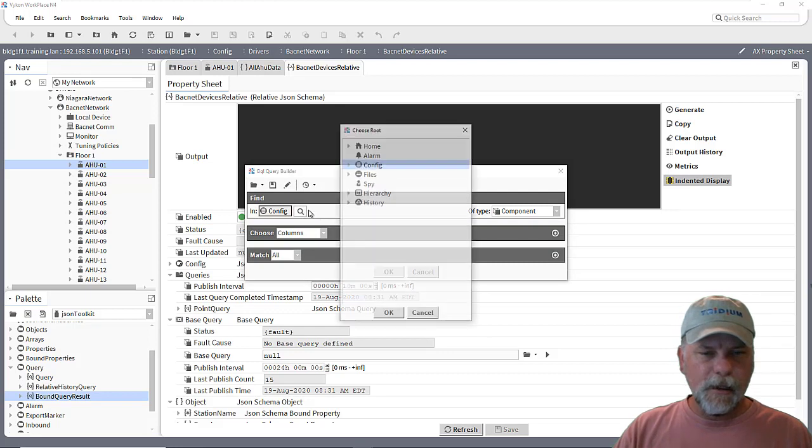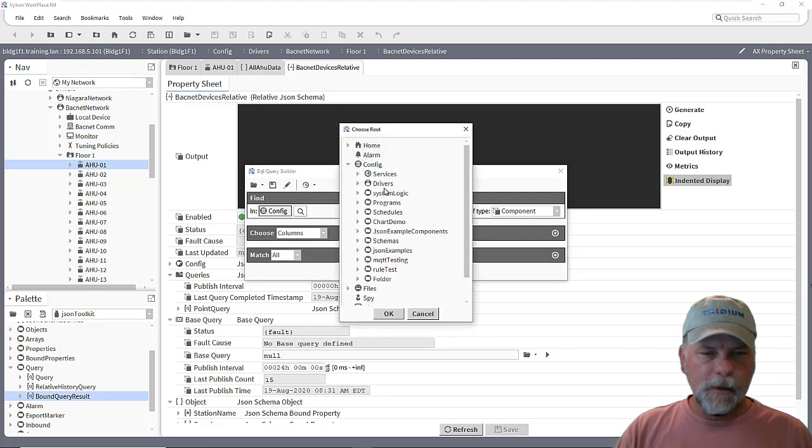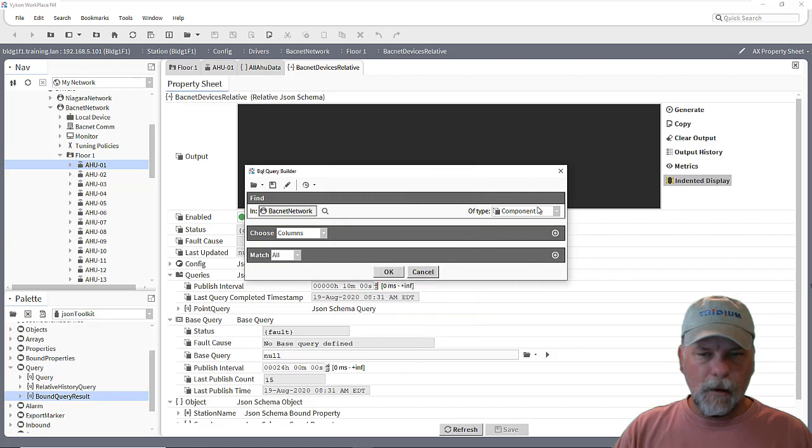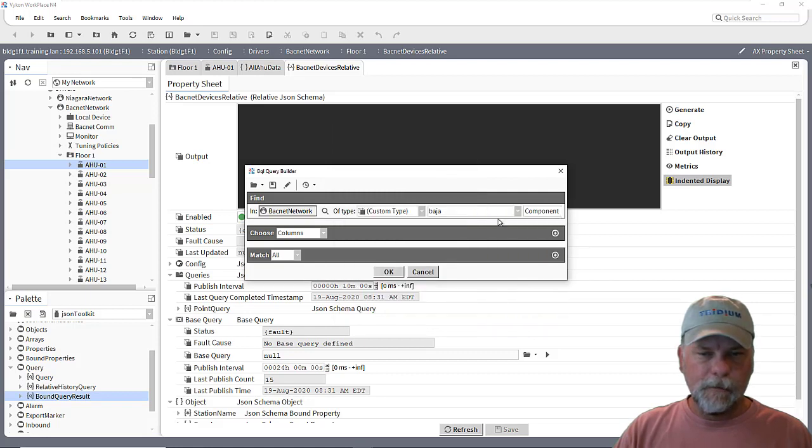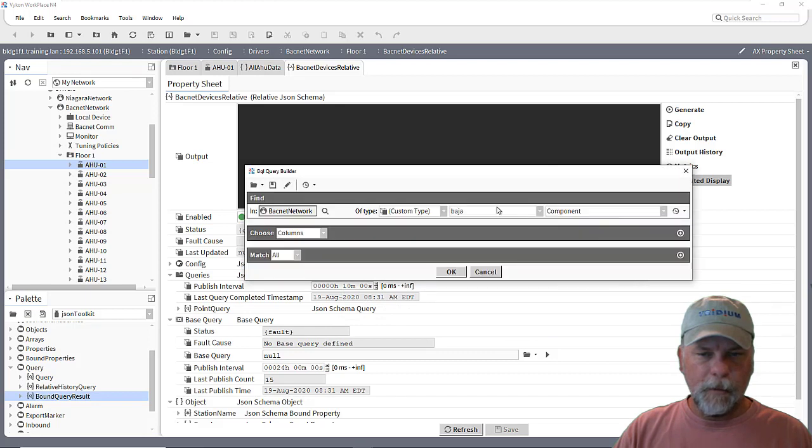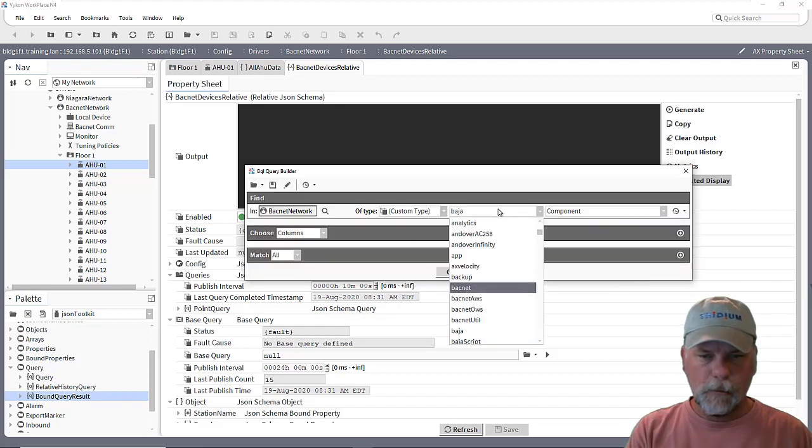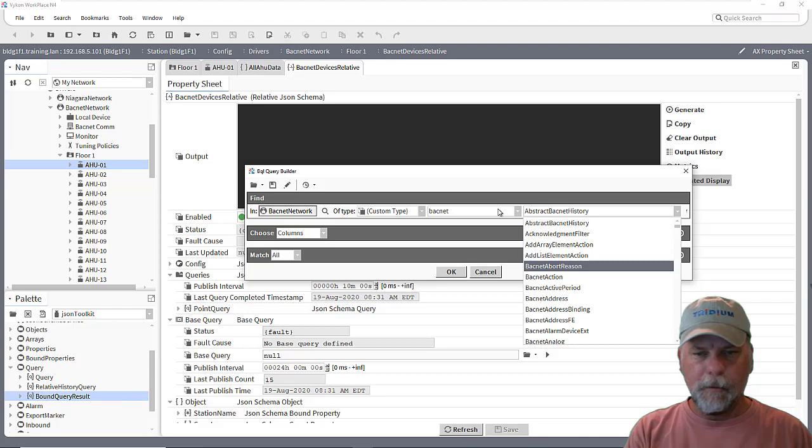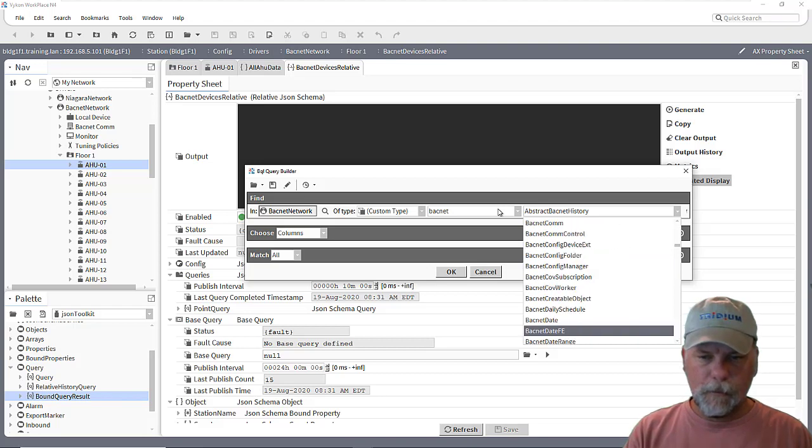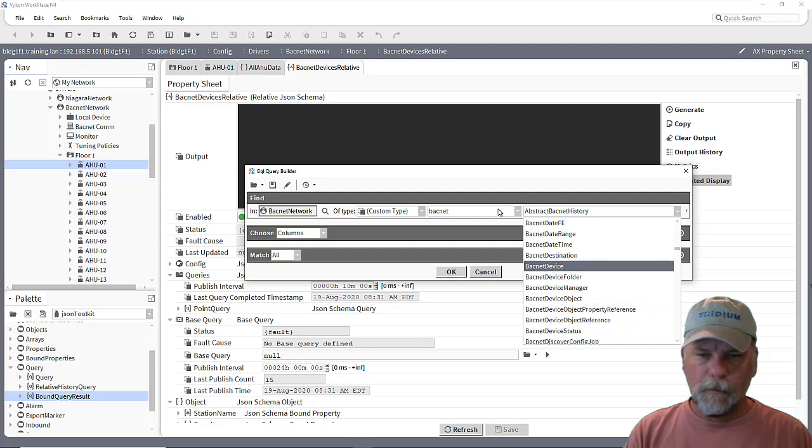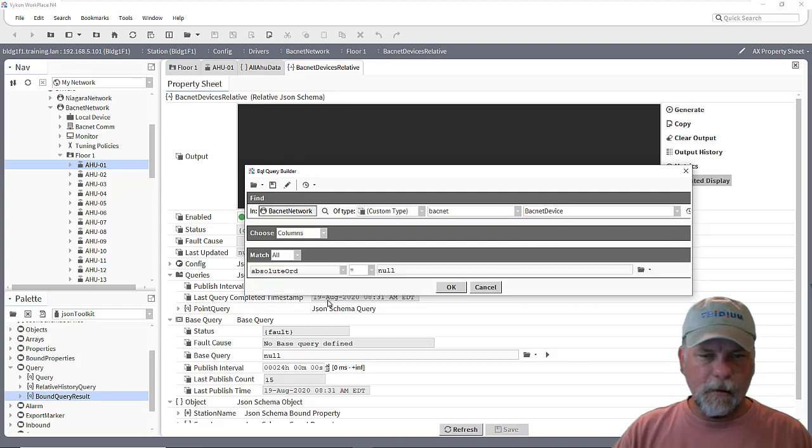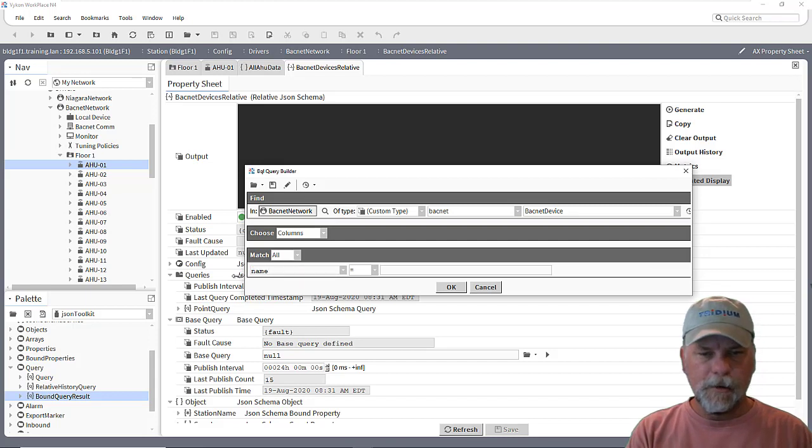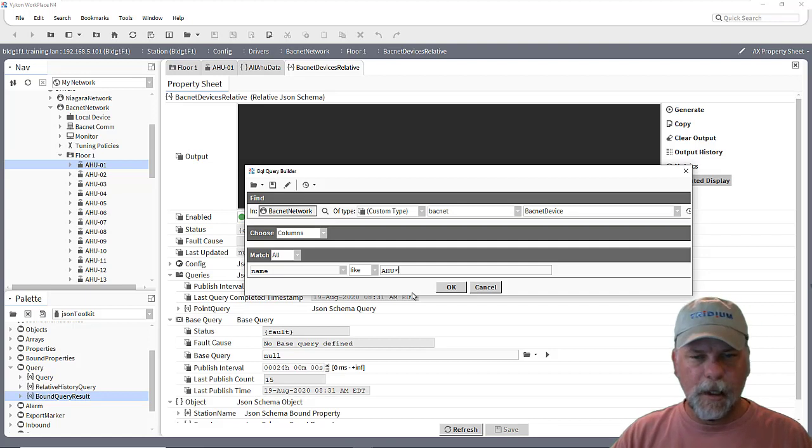So in this case I might look under the BACnet network and look for custom type and it'll be from the BACnet module and it'll be a BACnet device. And maybe a predicate where name is like AHU star or something along those lines.